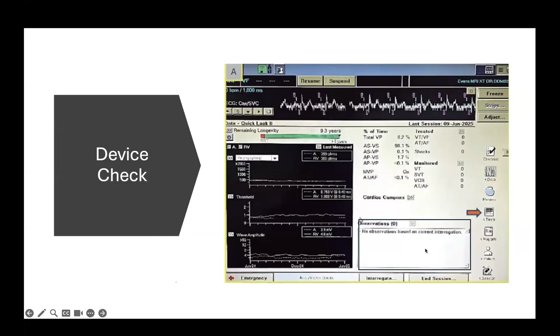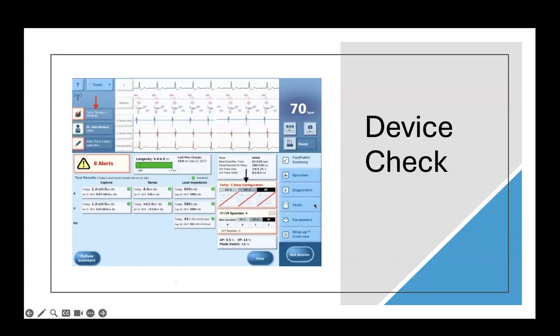This is the interface of Abbott devices, where basically it shows the same. So there were 8 alerts. The battery here is about 6 to 7 years. These are impedances, which seem stable, sensing, and the capture on the other side here. And then we go over the tests on the right side of the screen, and then we go over sensing, pacing thresholds, and impedances testing. On a Boston Scientific device, it's basically the same. So the summary will typically give you a hint or a clue about the general function of the device.